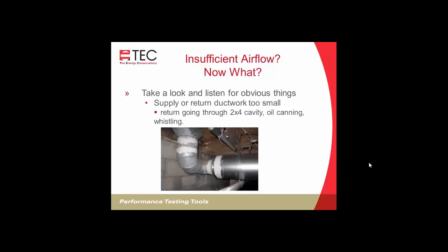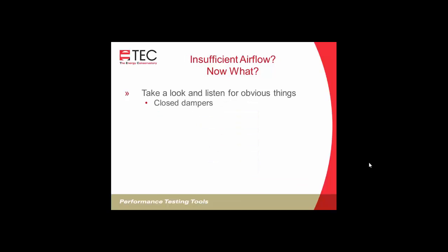Oil canning or oil panning, or there's a few different terms for that sound that you hear when the air handler comes on. You hear a banging sound because either the return is getting sucked in or the supply is getting pushed out as soon as the air handler comes on. So clearly, if it's enough to move the ductwork to make that kind of a noise when the air handler first turns on, then you've got some issues with restricted ductwork. Whistling is certainly an issue. You've got too much velocity trying to get through a small register, and you can hear the noisy sounds, and that's a pretty good indication that your ductwork is too small also. So looking and listening for some obvious problems.